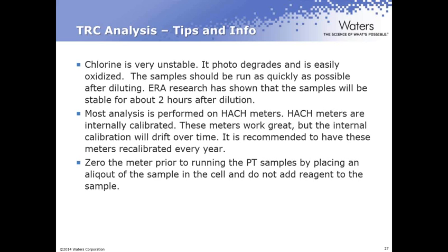So it's a recommendation to have those meters recalibrated once a year, and I know a lot of states will require that. But to prevent drift from happening and causing your values to be low, I'd recommend at least once a year to recalibrate the meters.